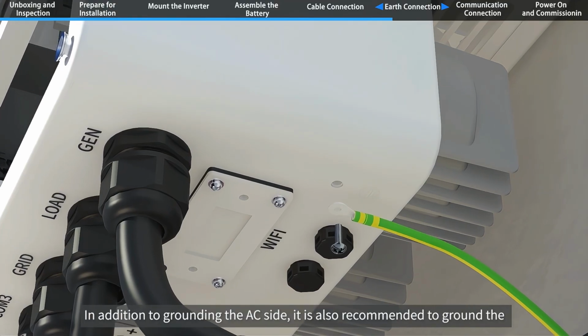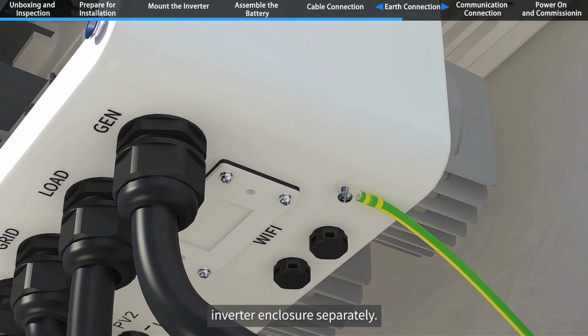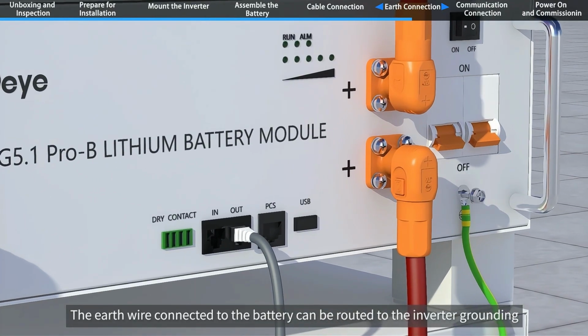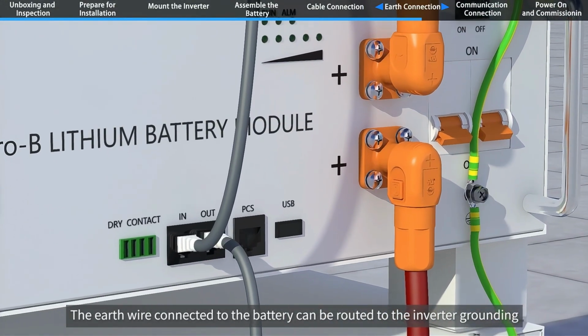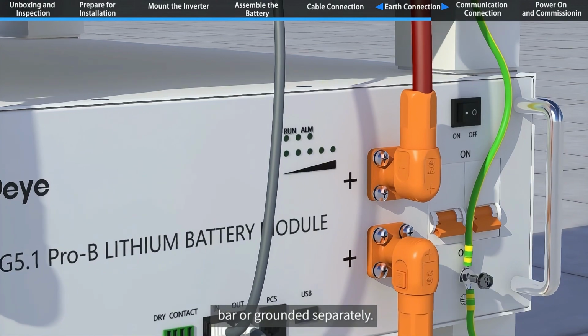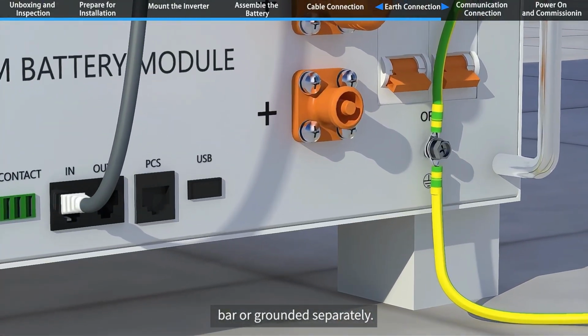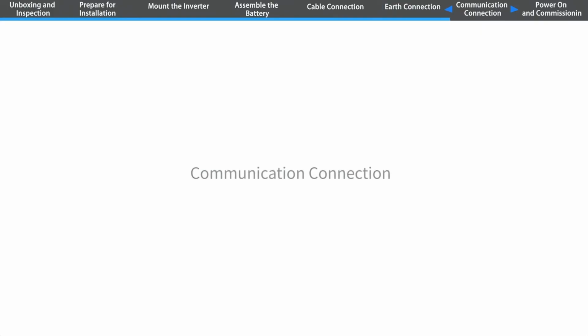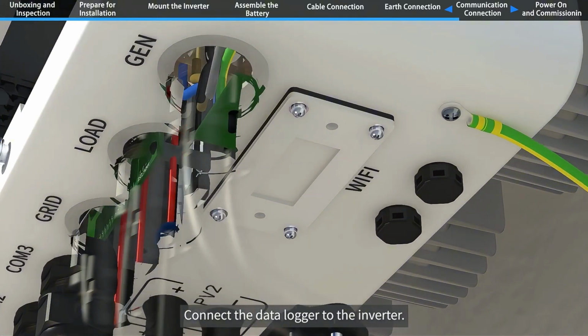In addition to grounding the AC side, it is also recommended to ground the inverter enclosure separately. The earth wire connected to the battery can be routed to the inverter grounding bar or grounded separately. Communication connection. Connect the data logger to the inverter.